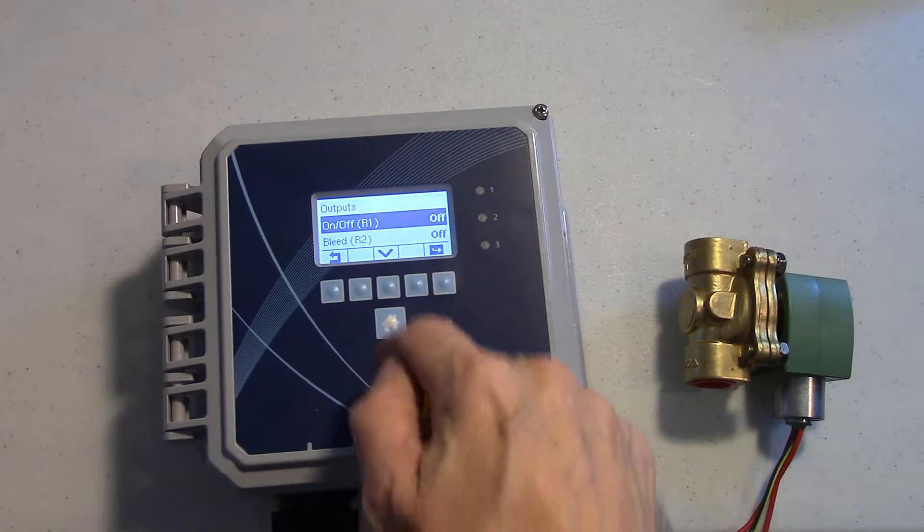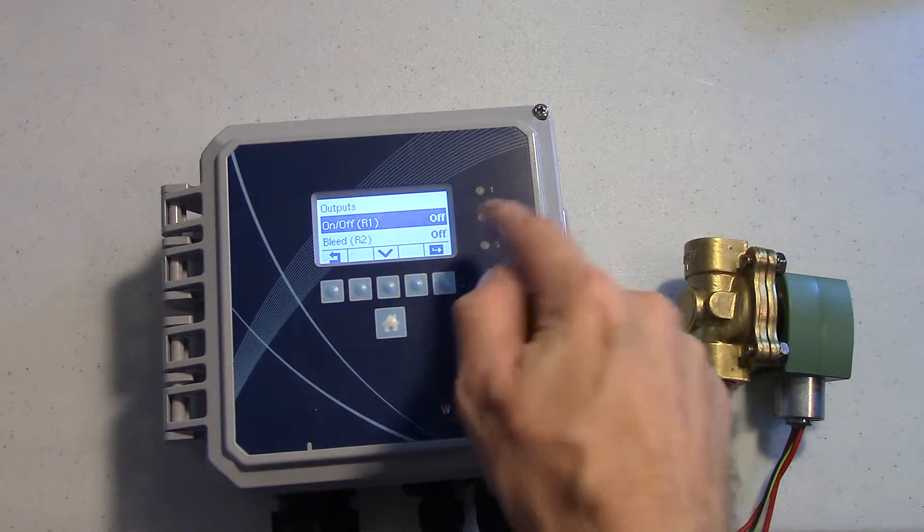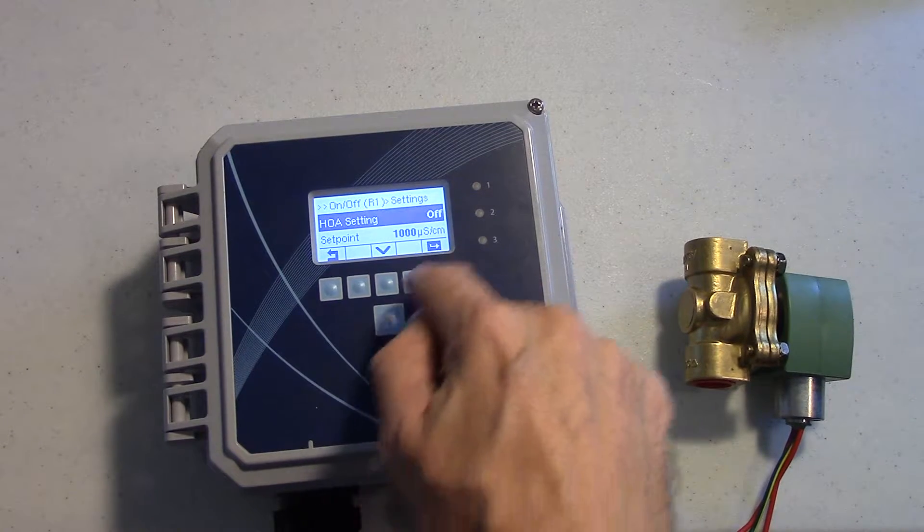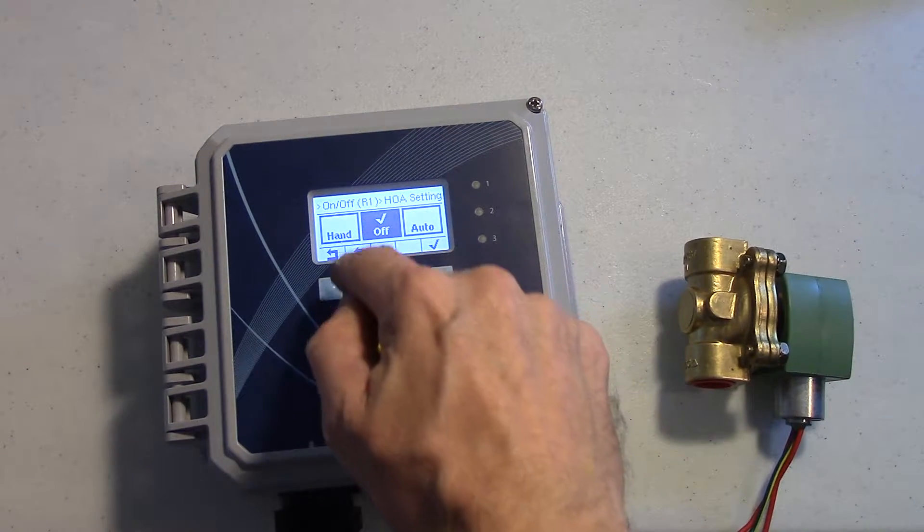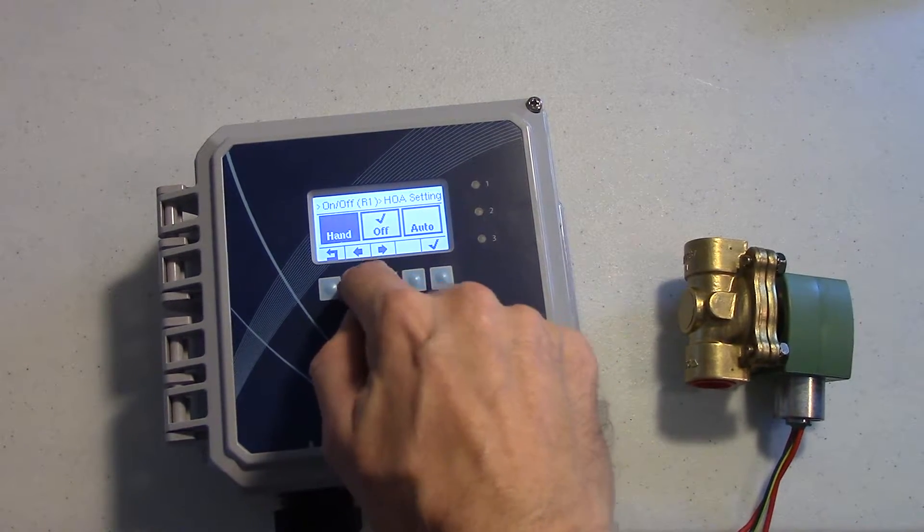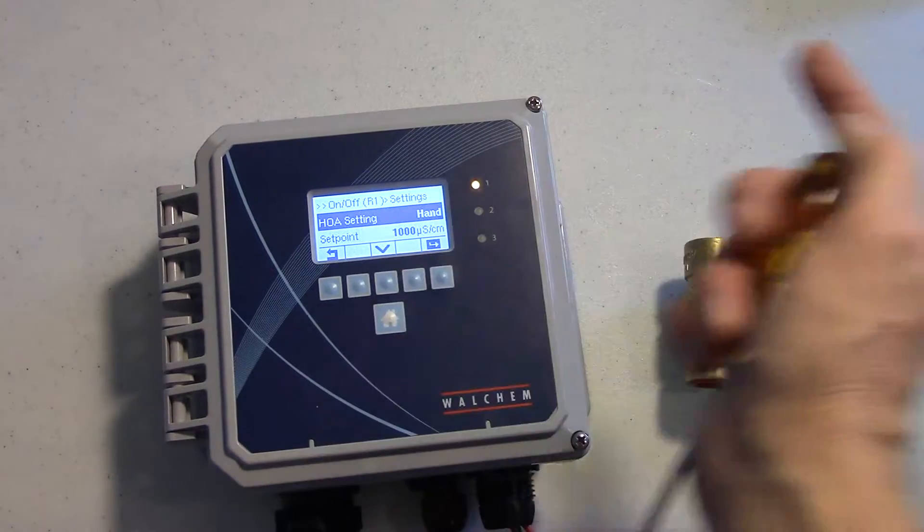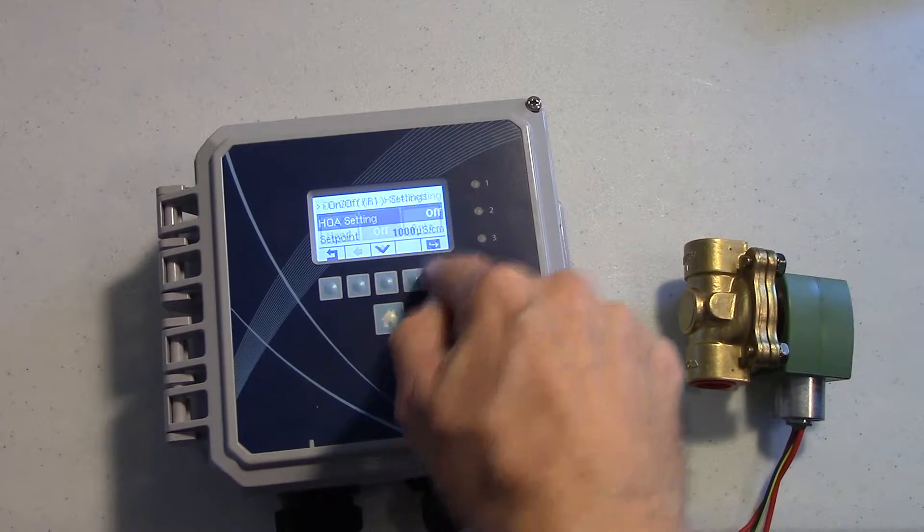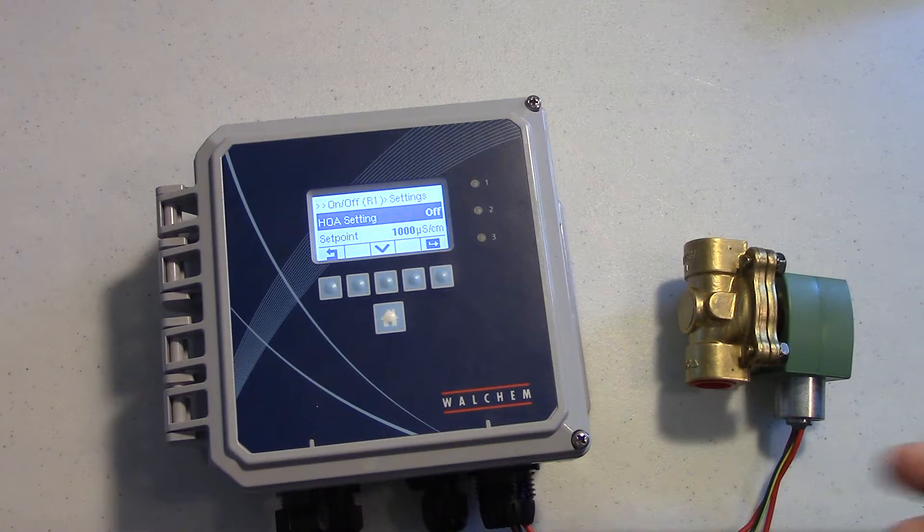So to get to the relays the down arrow, I've wired it to relay one, enter settings and I'm going to put it into hand. Hit the check, comes right on. Put it back off, turns off, everything's wired correctly.